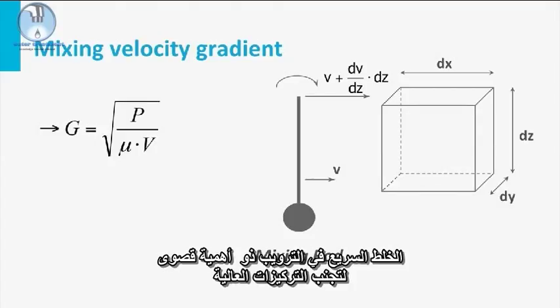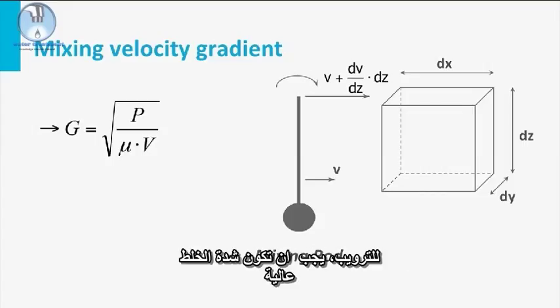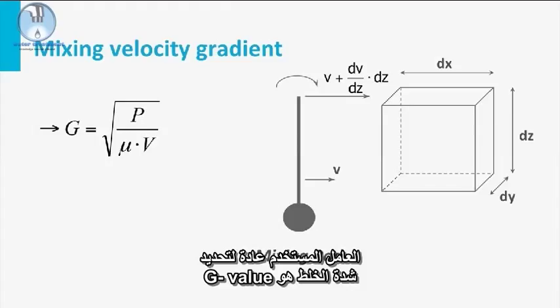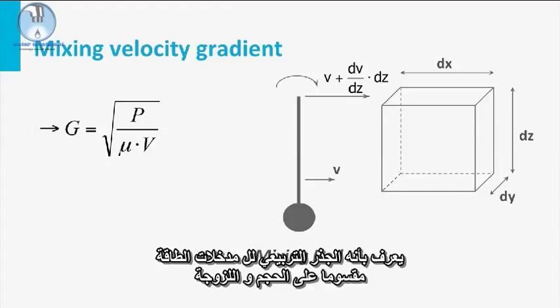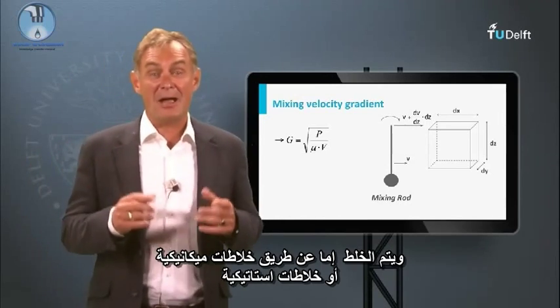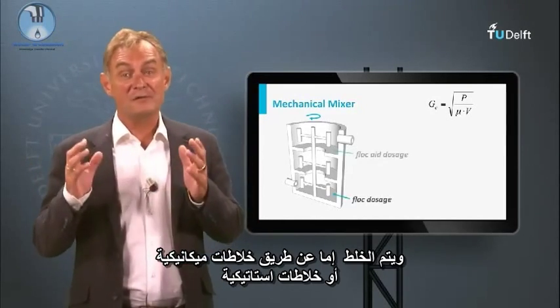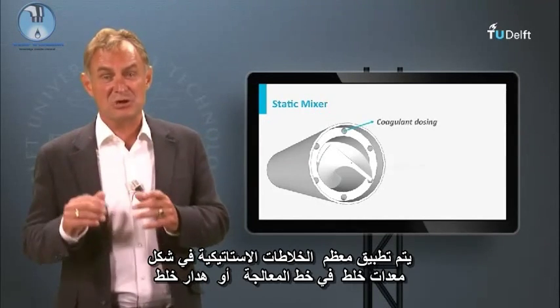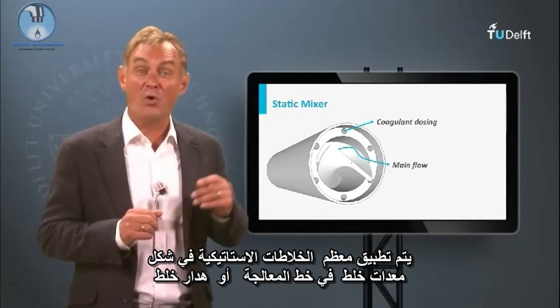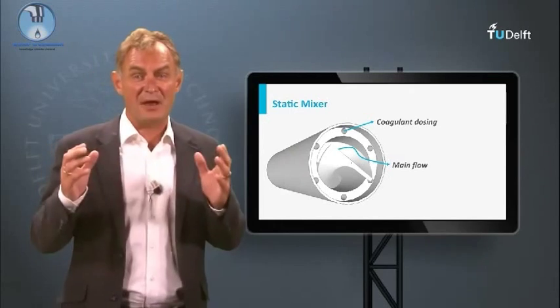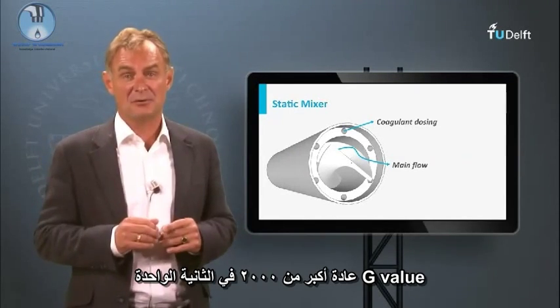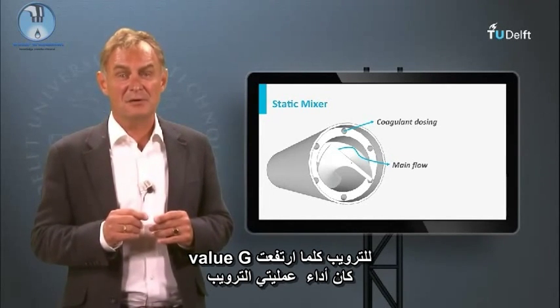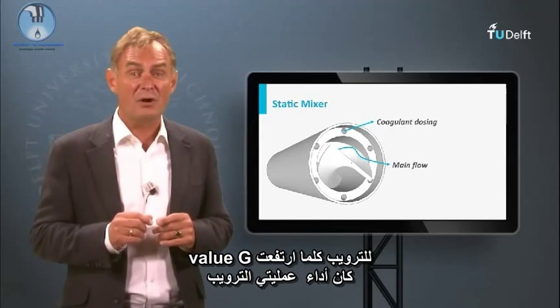Rapid mixing of coagulant is of utmost importance to avoid locally high concentrations of coagulant. For coagulation, the mixing intensity must thus be high. A commonly used parameter for determining the mixing intensity is the G-value, defined as the square root of the power input divided by the volume and the viscosity. Mixing is done by either mechanical mixers or static mixers — mostly static mixers in the form of inline mixing devices or weir mixers. G-values larger than 2000 per second are common, and the higher the G-value of coagulation, the better the performance of the coagulation-flocculation process.